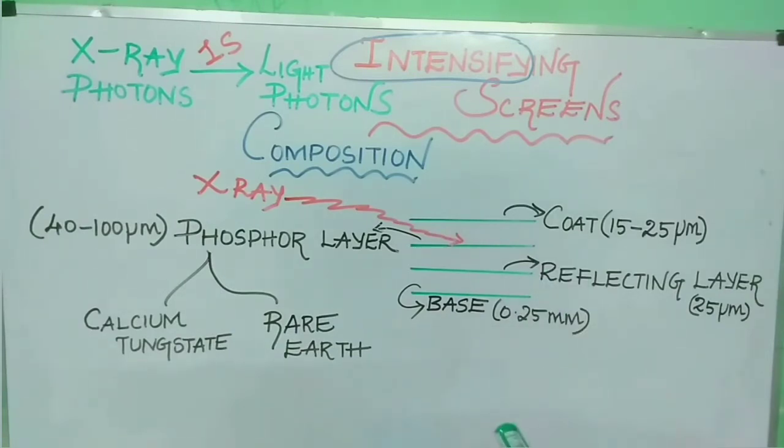Types of phosphors used in dental screens are calcium tungstate and rare earth phosphors. Calcium tungstate fluoresces or emits light in the blue portion of the spectrum. Whereas rare earth phosphors fluoresce in the green portion of the spectrum. Rare earth phosphors include gadolinium oxysulfide terbium activated, lanthanum oxybromide, and these rare earth phosphors are four times more efficient compared to calcium tungstate.